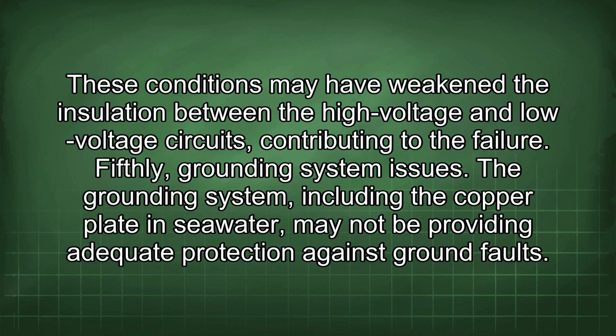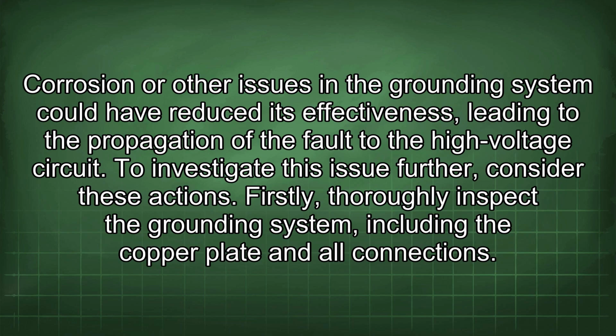Fifthly, grounding system issues. The grounding system, including the copper plate in seawater, may not be providing adequate protection against ground faults. Corrosion or other issues in the grounding system could have reduced its effectiveness, leading to the propagation of the fault to the high voltage circuit. To investigate this issue further, consider these actions.